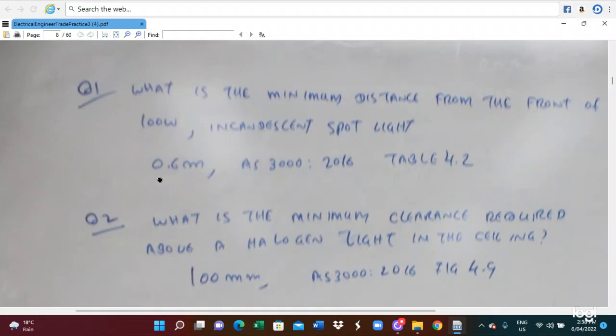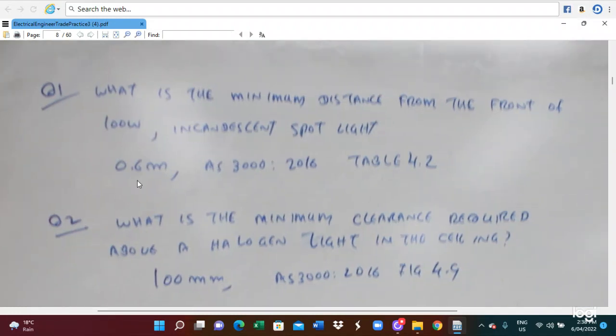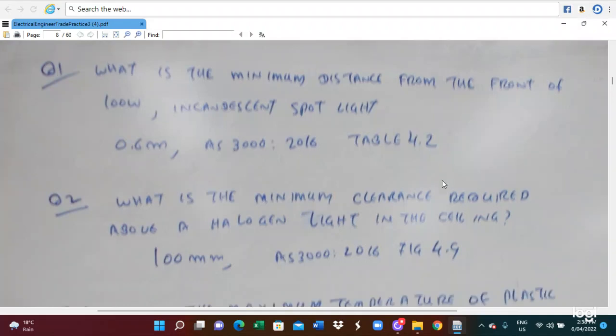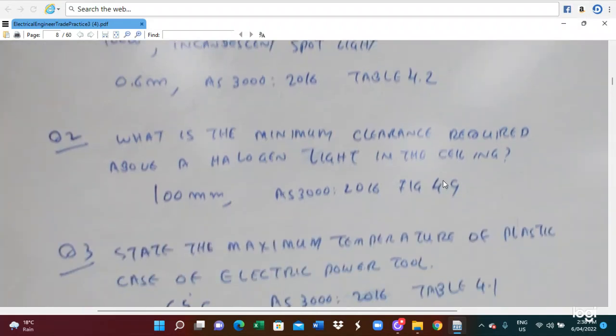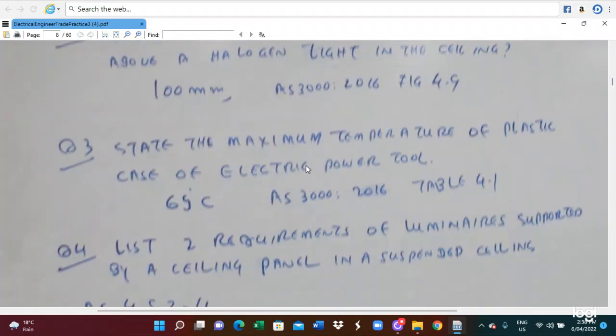So what is the minimum distance from the front of a 100 watt incandescent spotlight? In this case it should be 0.6 meter. We have to follow the AS3000 table 4.2. What is the minimum clearance required above a halogen light in the ceiling? So this is 100 millimeter. We have to refer to figure 4.9 of AS3000.